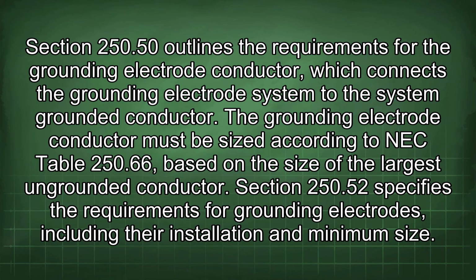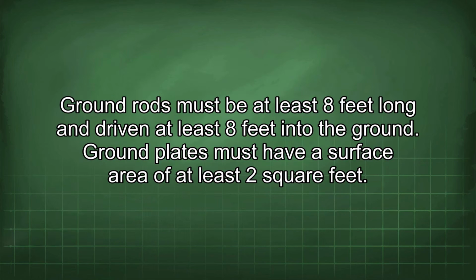Section 250.52 specifies the requirements for grounding electrodes, including their installation and minimum size. Ground rods must be at least 8 feet long and driven at least 8 feet into the ground. Ground plates must have a surface area of at least 2 square feet.